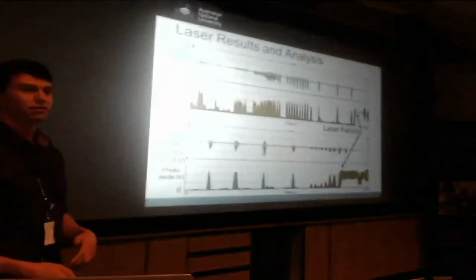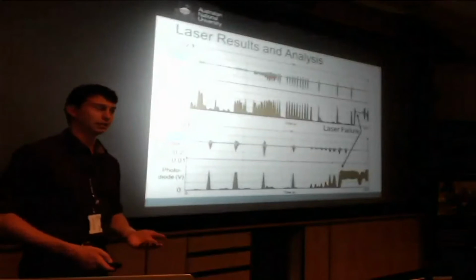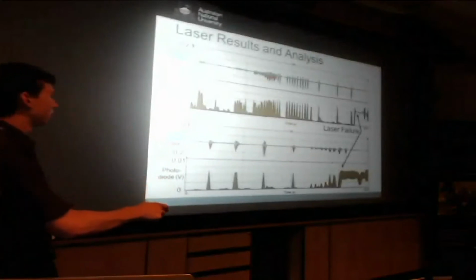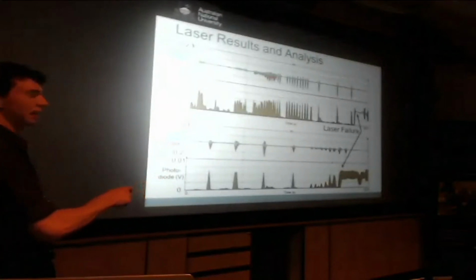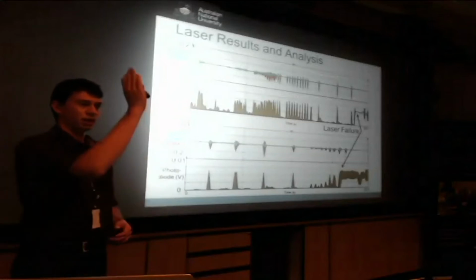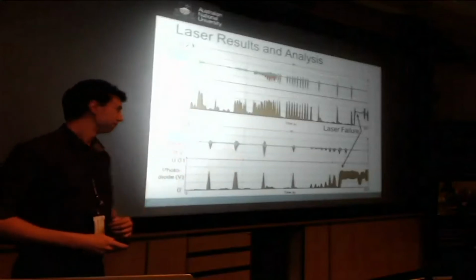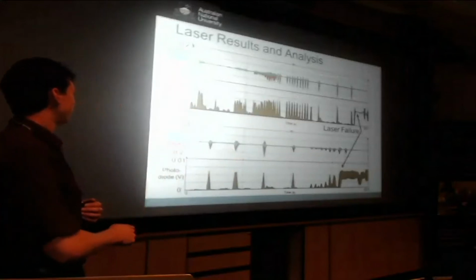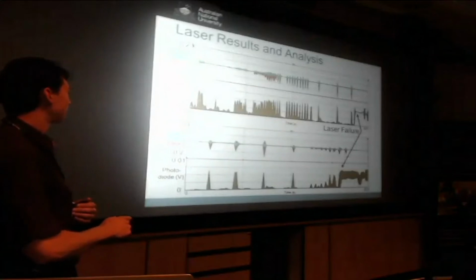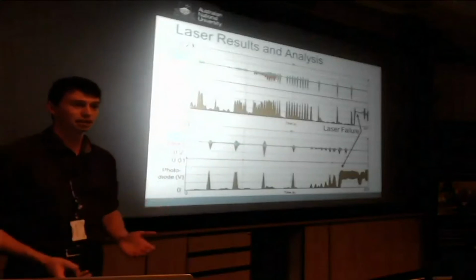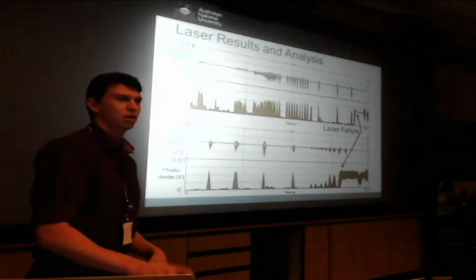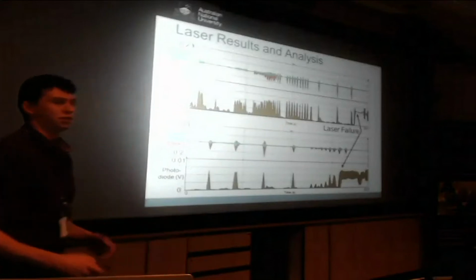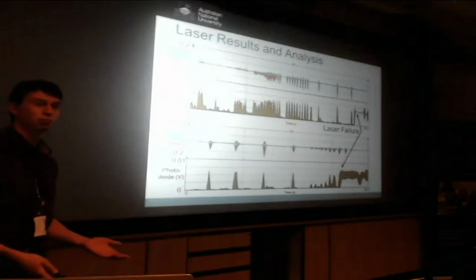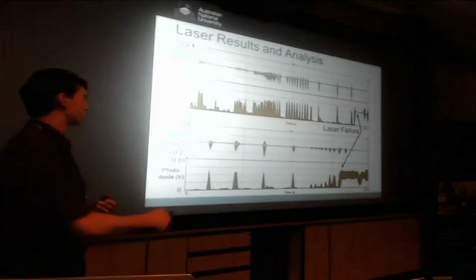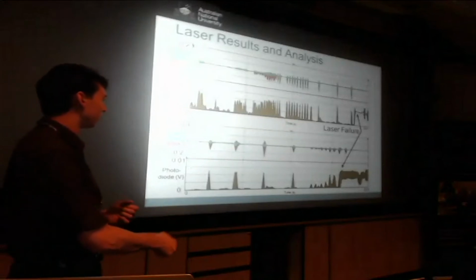What you can see here are a few time series of tests we did. On the top, we've got our vibrations in the X, Y, Z axes, which were just X, Y, Z in the laser room. On the bottom, we have the output of a photodiode, so the higher these peaks are, the more the laser is deteriorating. We kept tapping on the bench until the PID controllers could no longer compensate for the vibrations and the laser stopped working, which is what you see over here.